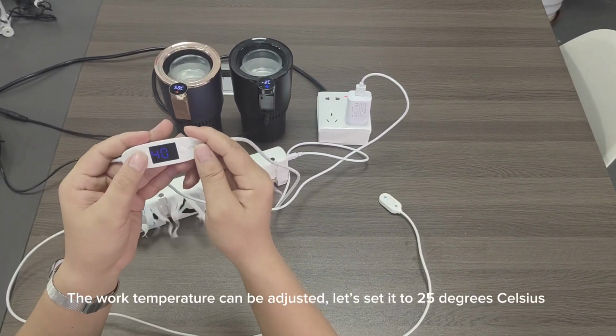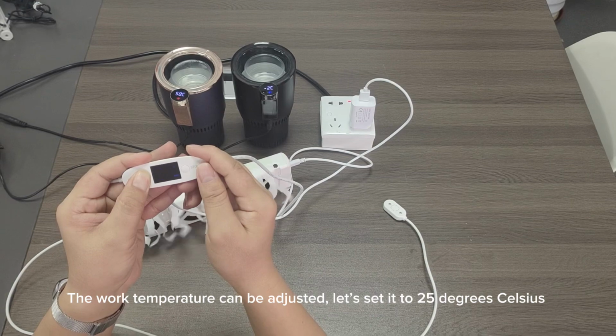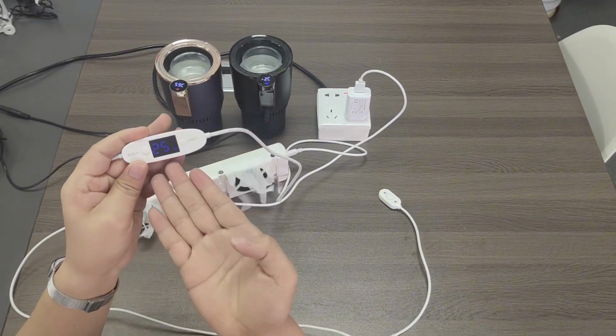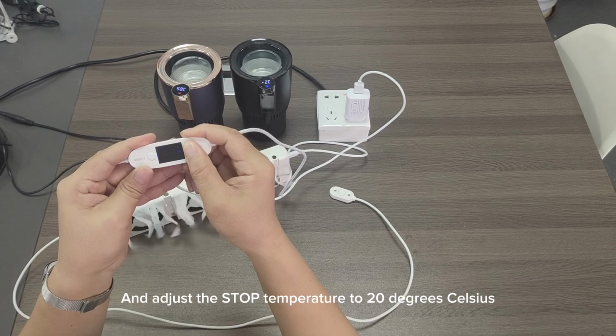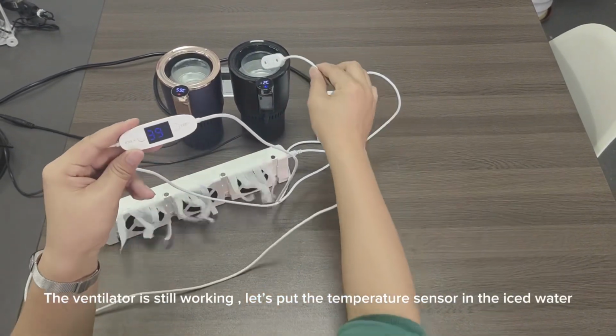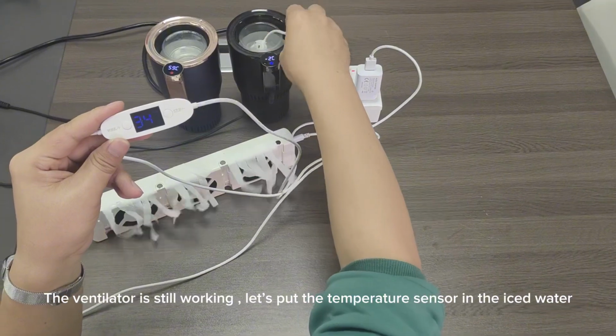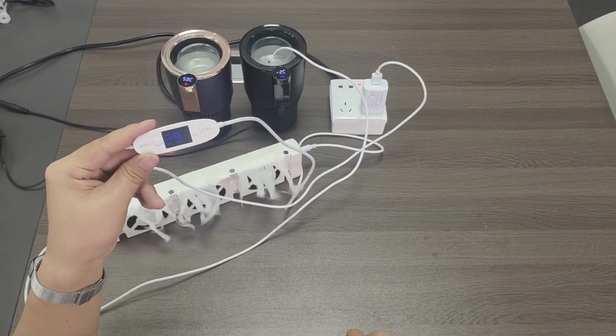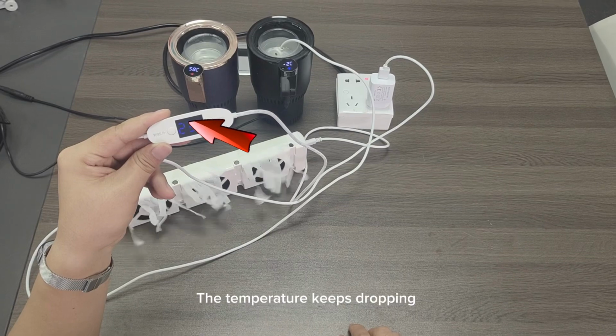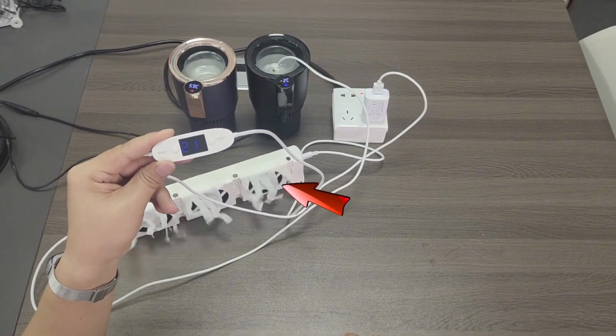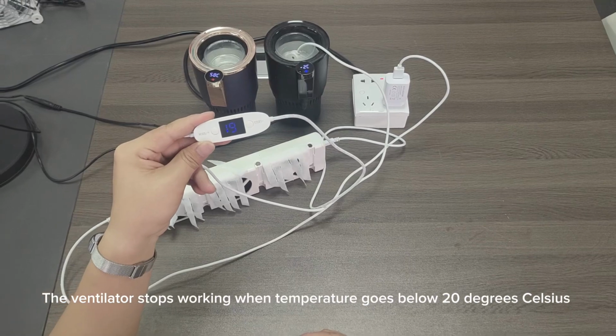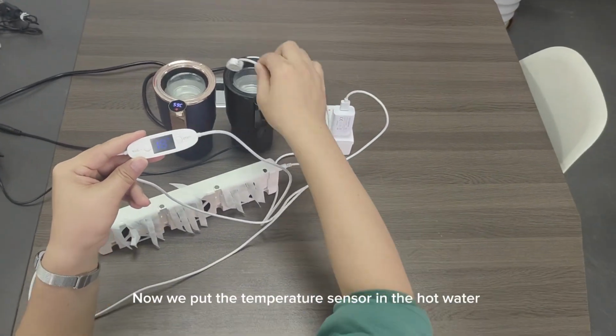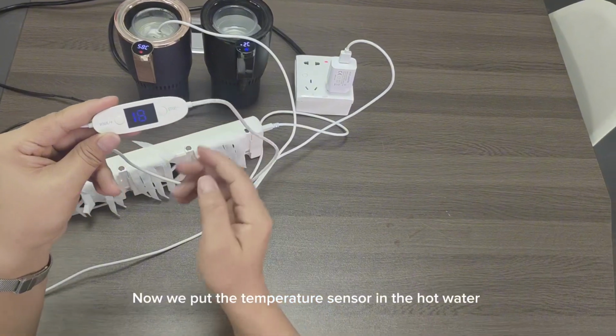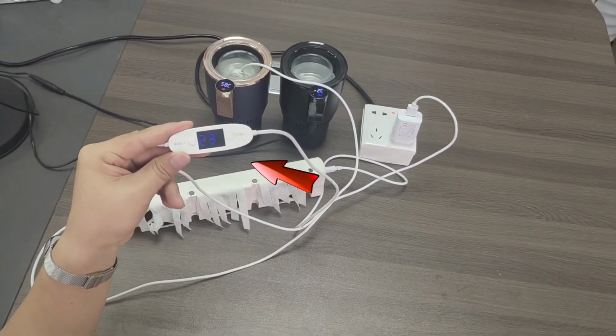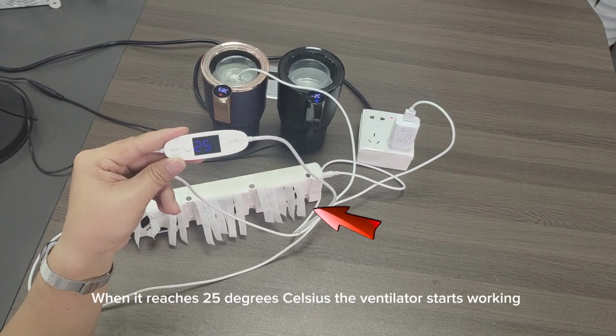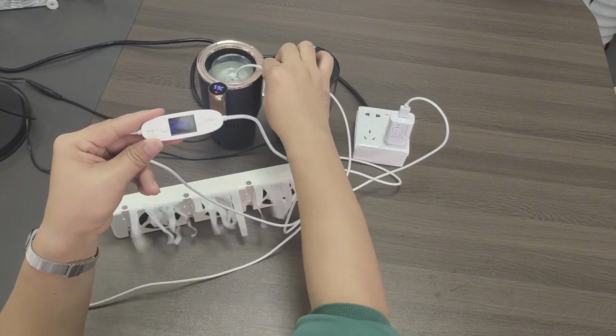The work temperature can be adjusted. Let's set it to 25 degrees Celsius. And adjust the stop temperature to 20 degrees Celsius. The ventilator is still working. Let's put the temperature sensor in the iced water. The temperature keeps dropping. The ventilator stops working when temperature goes below 20 degrees Celsius. Now we put the temperature sensor in the hot water. The temperature keeps rising. When it reaches 25 degrees Celsius, the ventilator starts working.